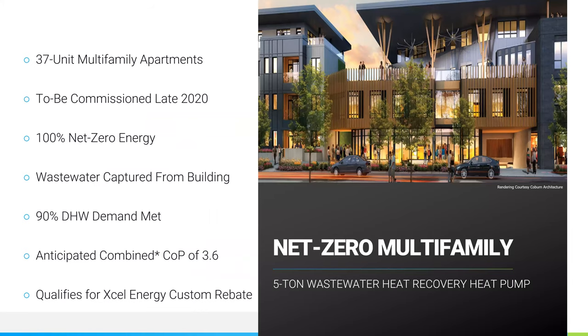Another project was in Boulder, Colorado, a 37 unit multifamily apartment complex. It'll be commissioned later here at the end of the year. It is 100% net zero, and does have a full photovoltaic system that coats the roof. All the wastewater energy is captured from the building. The wastewater heat recovery heat pump captures about 90% of that domestic hot water, or rather provides 90% of that domestic hot water for the building. And then there's an electric resistance water heater that provides that kind of top up.